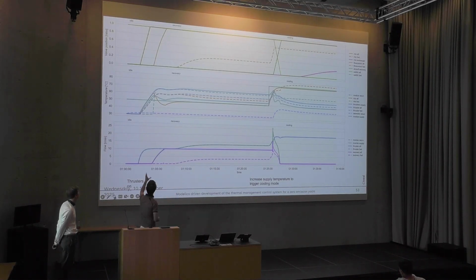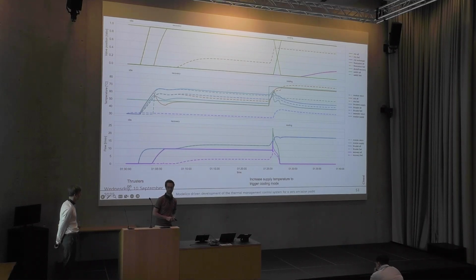So we start with the thrusters in idle. This is also an external value coming in from the propulsion control system. Then we start the thrusters up. First we go into recovery because that's always the best option. And you see the temperature in the middle starts ramping, and at one point the temperature is reached. Then the flow to the consumers starts to increase, and the valve opens. So first it recirculates, and then it starts releasing when the temperature is reached.